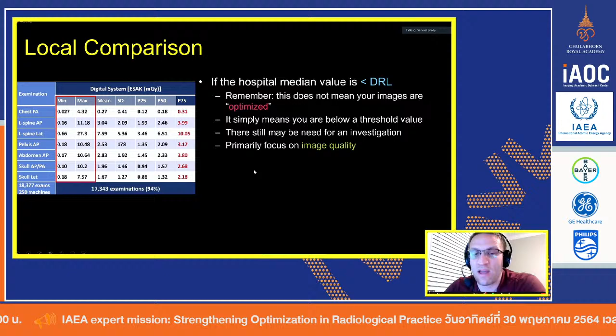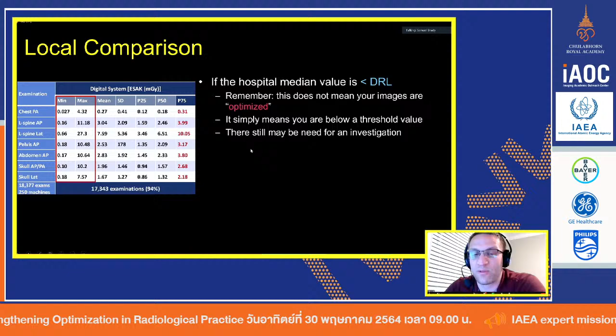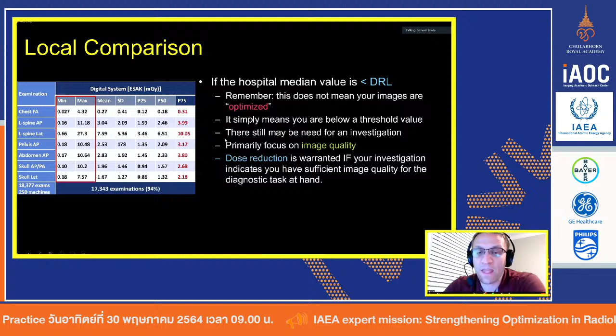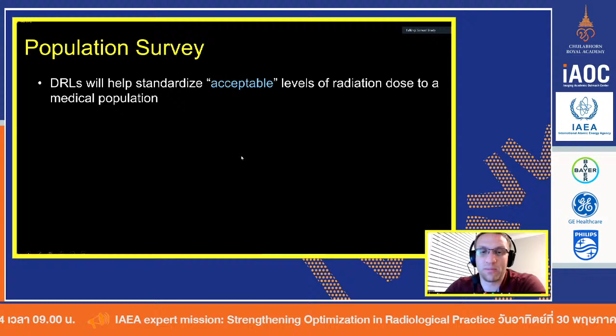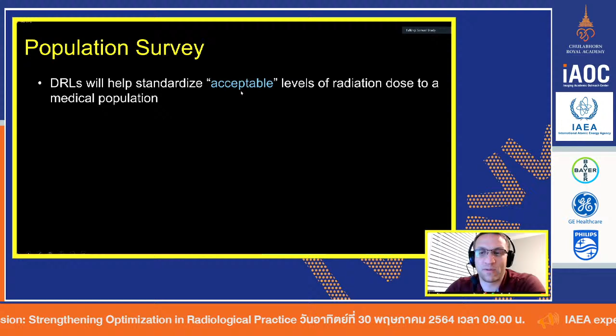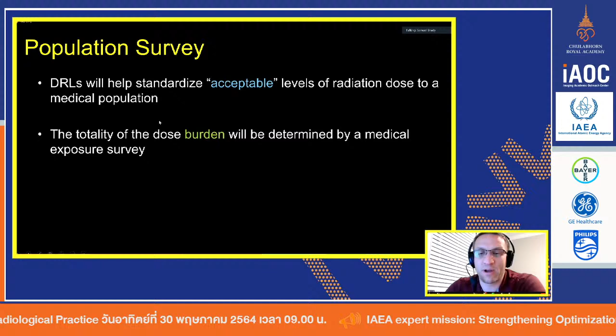For any protocol or exam that has doses less than the DRL, the primary focus should be making sure the image quality is where it's at and appropriate. If you do choose to continue to reduce the dose, it should always be based on image quality based assessments. So the DRLs help us standardize an acceptable level for radiation dose in a medical population. The actual total dose burden of the population is a completely separate survey.